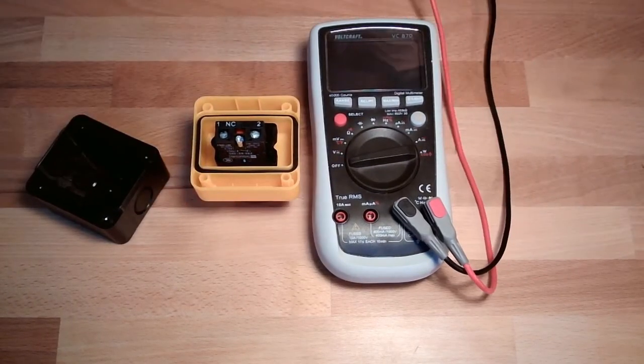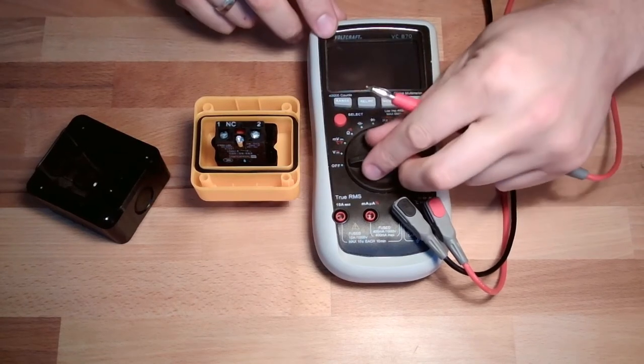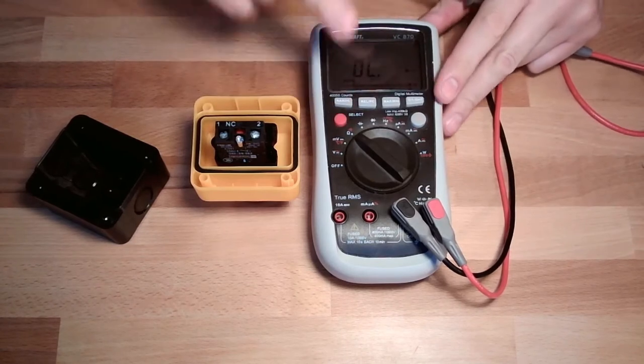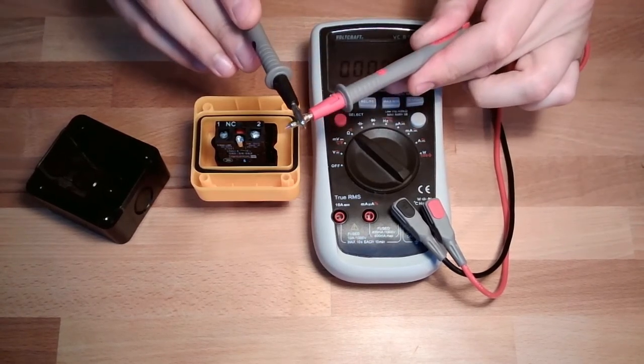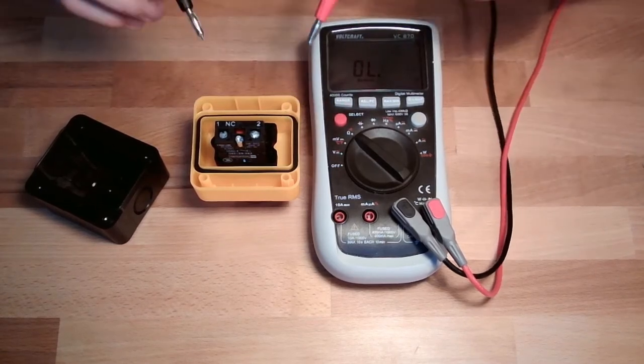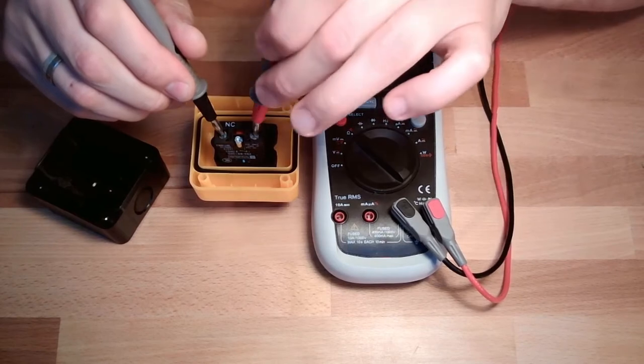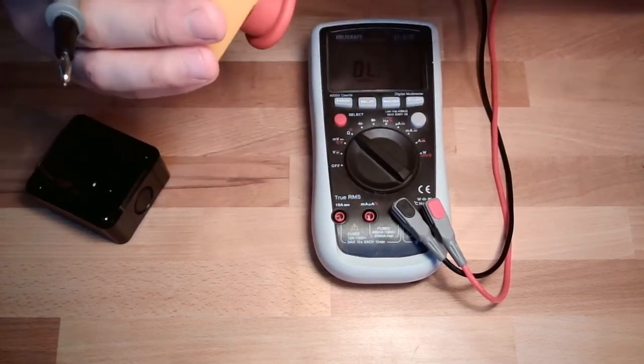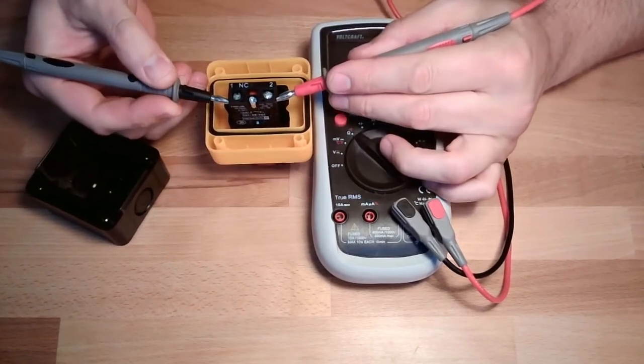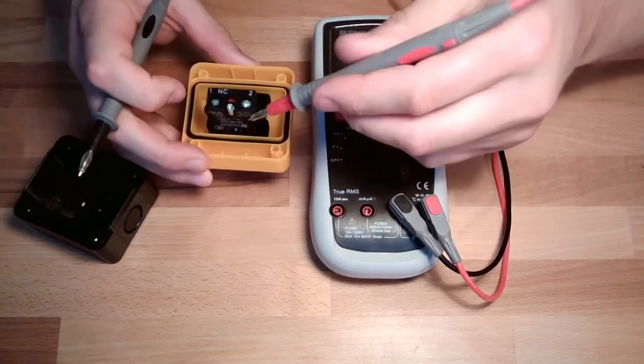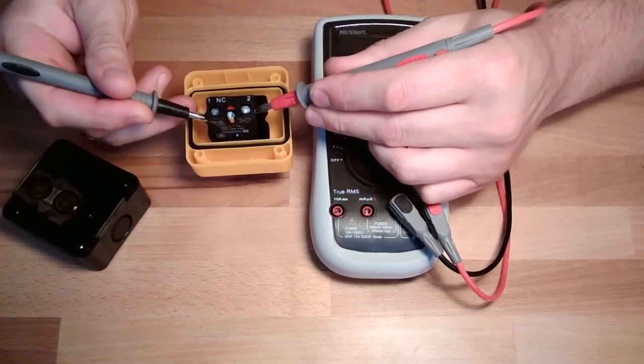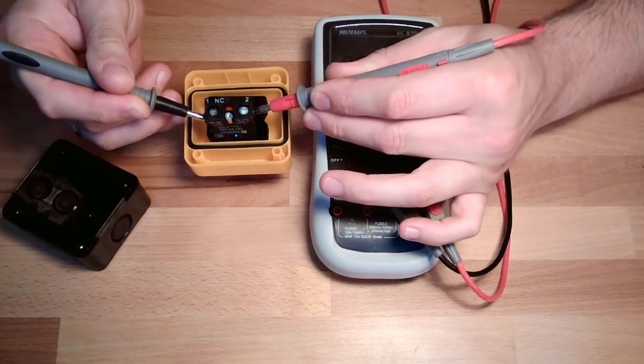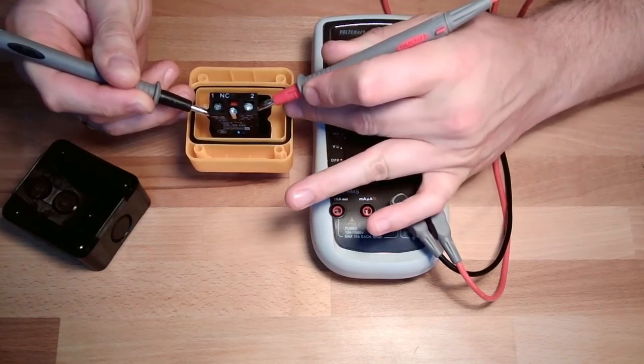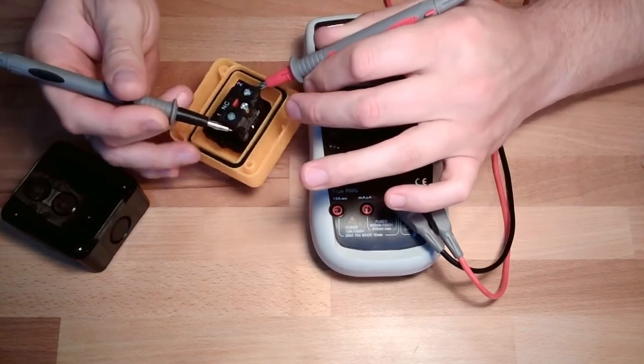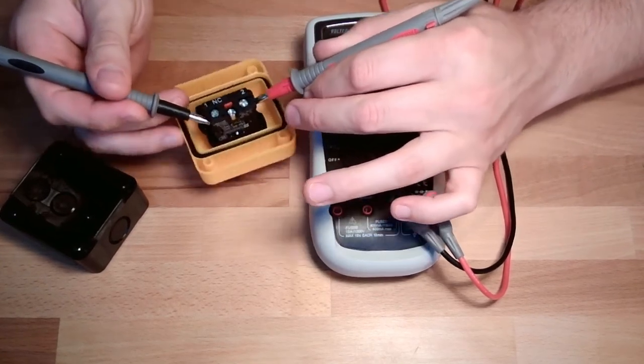Let's hope the battery is working for this. I will switch it to ohm measurement and turn on the beep. This means every time we have contact, we hear a beep. If I now check the connection, is it pressed? No. It's nothing. Check connection. Aha, okay, it's again the screw stopping. You see, it is connected. And now it's no longer connected. Now it's operated. So it's normally closed.